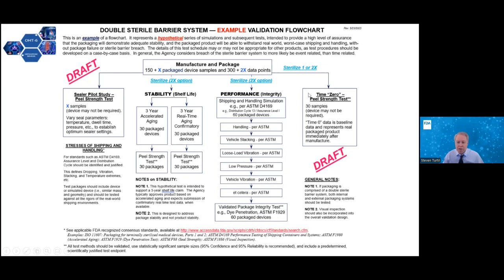There's also, in the very last column on the right, time zero peel strength testing, because the second column that you're looking at, the stability test, is giving you a shelf life to make sure that it can maintain product sterility for, in this case, 3 years. We also want to know, what if the product shipped immediately and used immediately? We want to know that that seal is adequate. So we also want to know that you're doing time zero peel strength testing. Again, 30 samples is ideal.